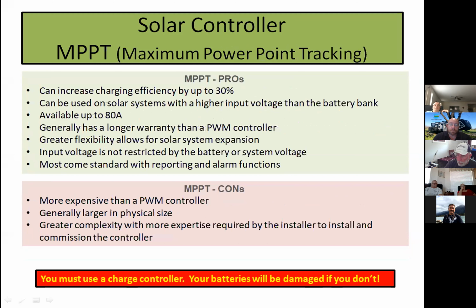Another controller you can use, and by far the one most installers use now, is an MPPT, or Maximum Power Point Tracking controller. It's a little more expensive than a PWM but provides much more efficiency—typically about 30% more. You can get them with capabilities up to 80 amps, and with much higher voltage banks than a PWM controller. They normally have a longer warranty and are very flexible if you want to expand the size of your solar charging bank.